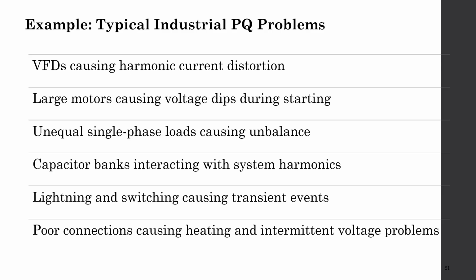As an example, typical industrial power quality problems. VFDs cause harmonic current distortion. Large motors cause voltage dips during starting. Unequal single-phase loads cause unbalance. Capacitor banks interact with system harmonics. Lightning and switching cause transient events. Poor connections cause heating and intermittent voltage problems.